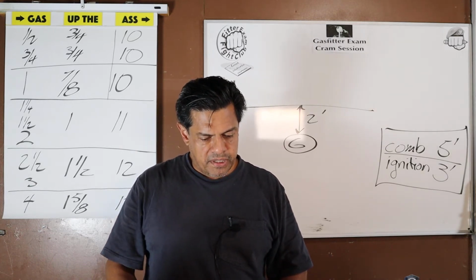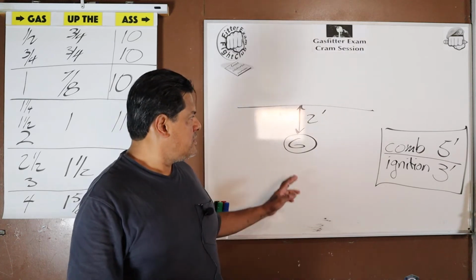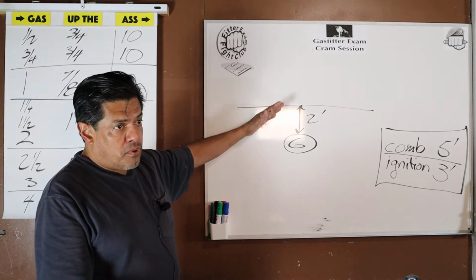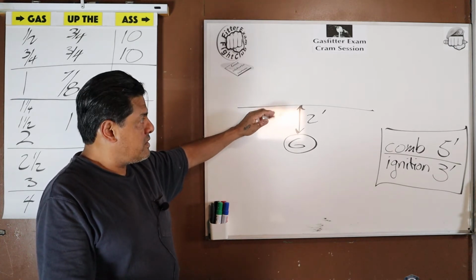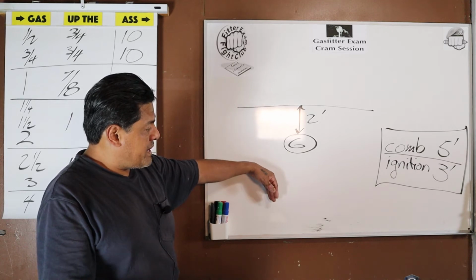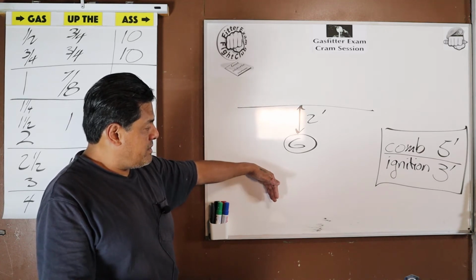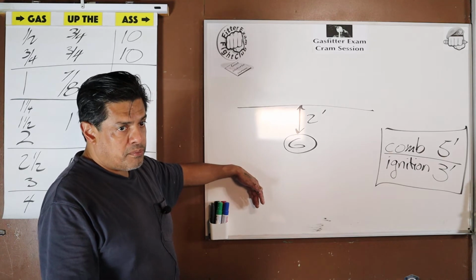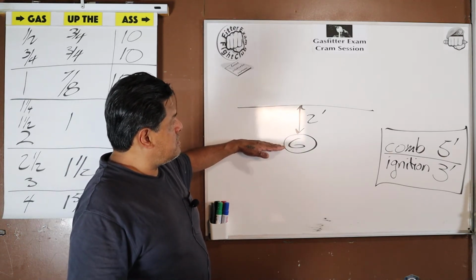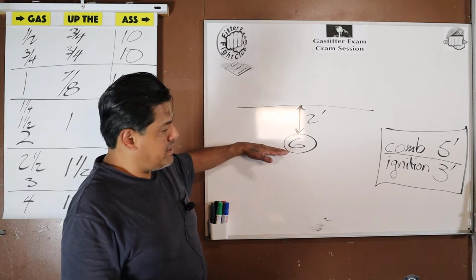I believe I was mentioning that the number 2 is a good number, because this is 2 feet or 24 inches. Remember, take your pick however you want. The control valve for the gas inside the building is no more than 2 feet from point of entry. The service is no less than 2 feet below grade.